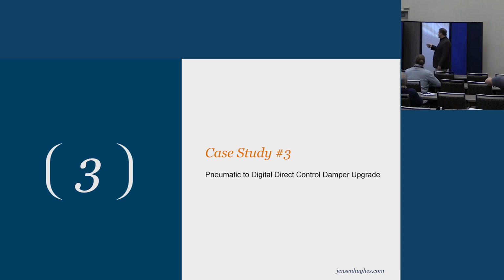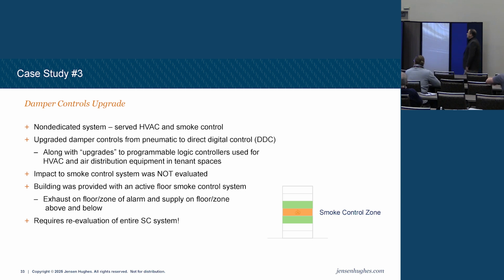Pneumatic to digital controls, pretty common as well. So damper controls upgrade. This one's probably not as common anymore. 10, 15 years ago, this was really common. You know, the pneumatic controls were pretty antiquated. Now I would imagine most buildings have probably already gone over to that, but a lot of non-dedicated equipment is shared, so my air handlers may be running on pneumatics, but they may also be doing double duty. We upgrade the dampers and all the controls to digital direct control. Along with the upgrades, we go to all PLCs.